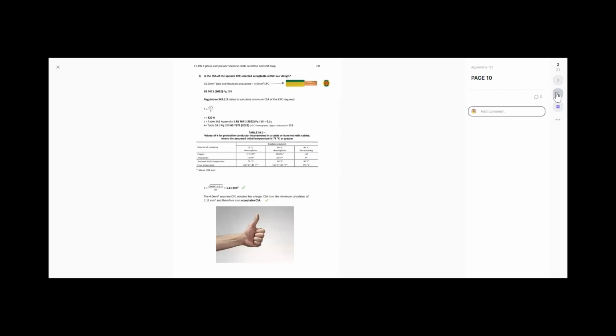Right, then, the last thing we've got to check is our 4 mil CPC that we've selected, that we're going to run alongside this SWA. We've got to make sure that the cross-sectional area of that cable, 4 mil, is acceptable based on that amount of fault current, based on that duration of time before the device disconnects, and based on the coefficient of the material that's used, in this case, copper. So last week, we had a look at Regulation 543.1.3, which talks about the minimum size CSA of the CPC that's required. And it gave us the old adiabatic equation.